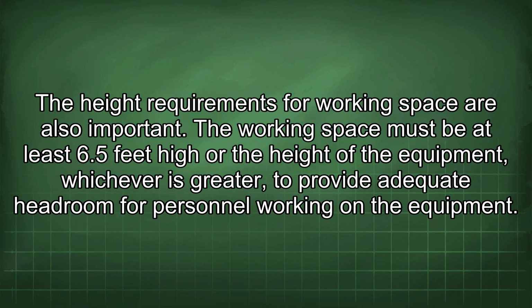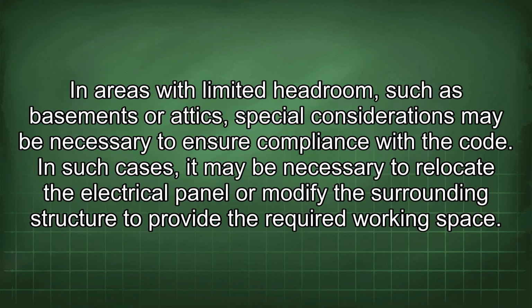The height requirements for working space are also important. The working space must be at least 6.5 feet high or the height of the equipment, whichever is greater, to provide adequate headroom for personnel working on the equipment. In areas with limited headroom, such as basements or attics, special considerations may be necessary to ensure compliance with the code.